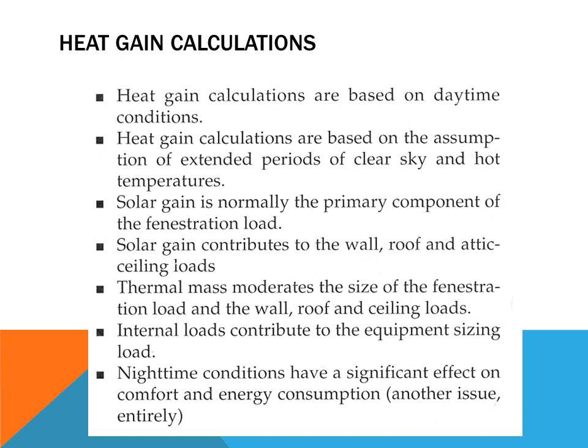When we look at heat gain calculations, there are many things we need to consider. Some are based on outdoor temperatures — specifically daytime conditions, because at nighttime there is usually no sun shining through the windows to add additional heat. But we do look at solar gain, which adds additional radiant heat we need to consider for sizing the air conditioning equipment. We also look at the thermal mass of the materials and fenestration loads, which result from the sun shining through windows, as well as loads based on the color of materials and how materials conduct heat.